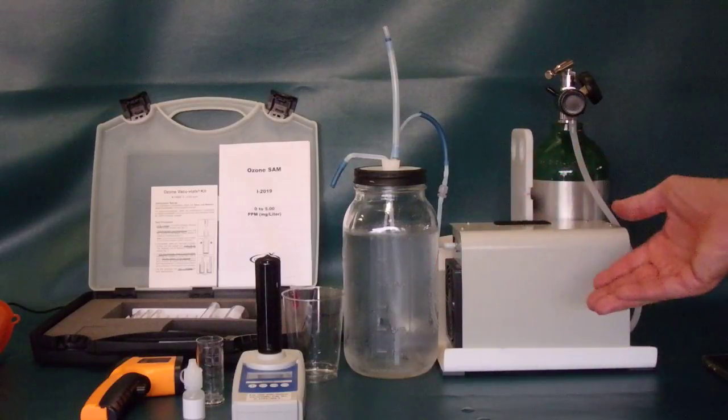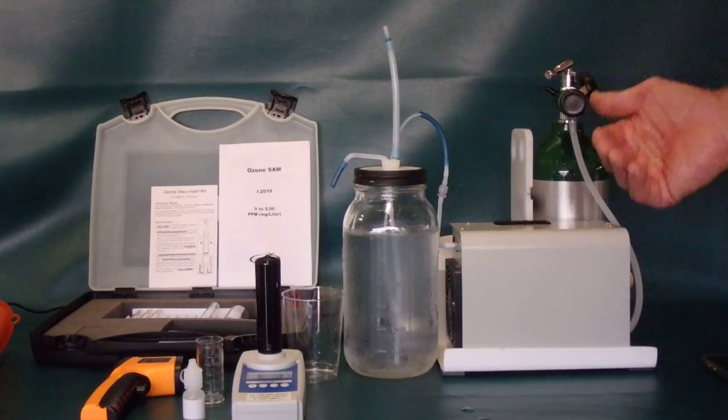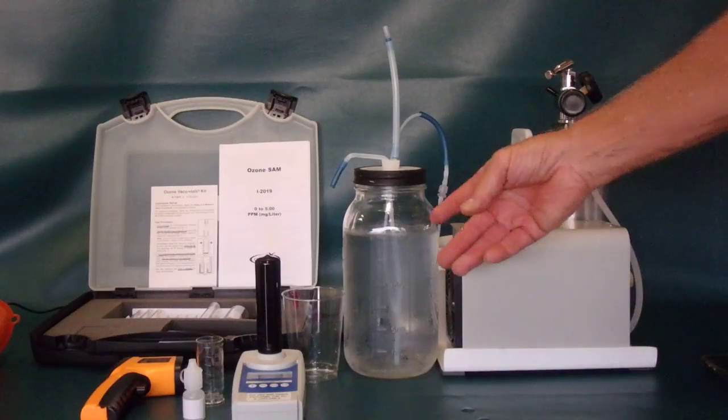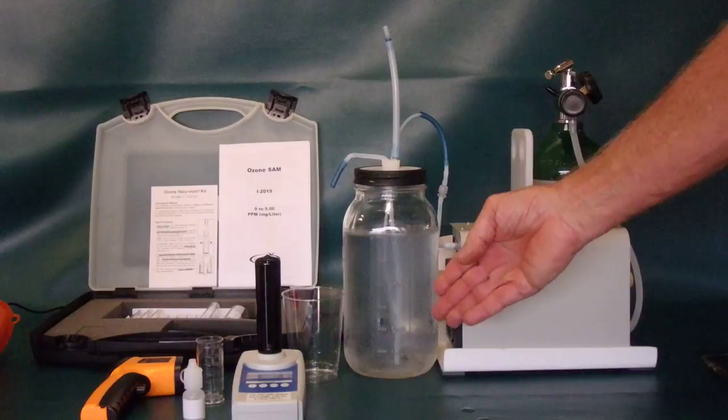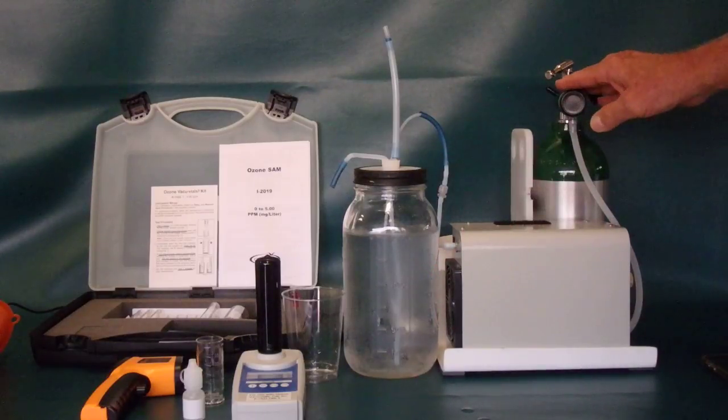And it also is the highest concentration for this system. Using more oxygen is not going to give you a higher concentration, but it will actually give you a lower concentration of ozone in the water. So it's very efficient. It produces highly ozonated water at one thirty-second liter per minute.